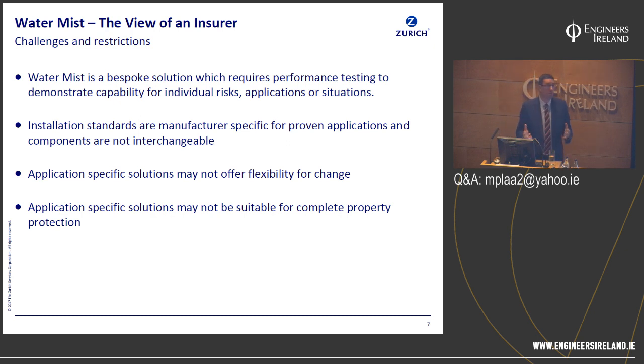And components are generally not interchangeable. You can't simply swap out one manufacturer's head for another manufacturer's head, because the spacing, the spray pattern and the testing are different. So it's important to remember that components are generally not interchangeable. And because the applications are specific, often they're not suitable for property protection as well. So it's about understanding whether that application is suitable.